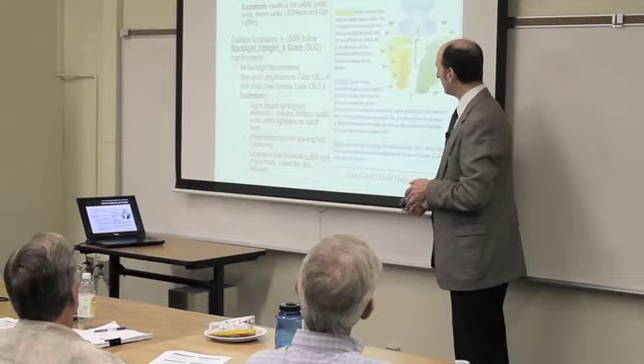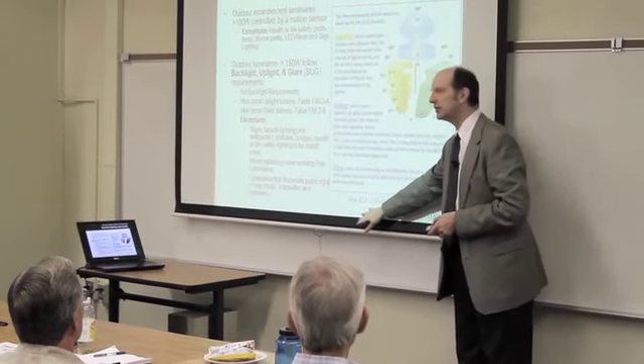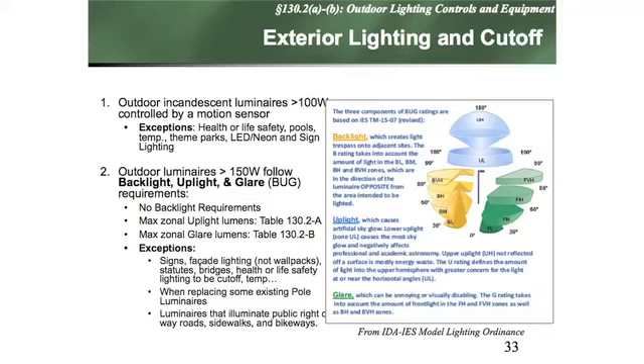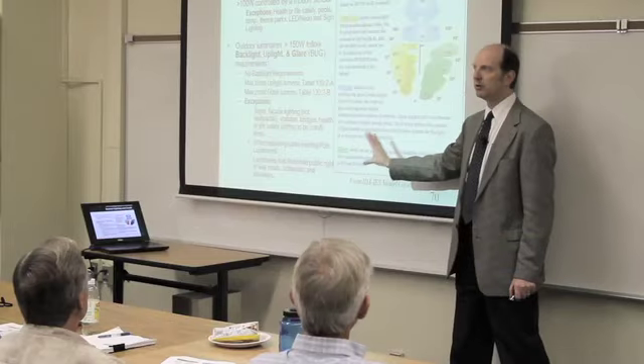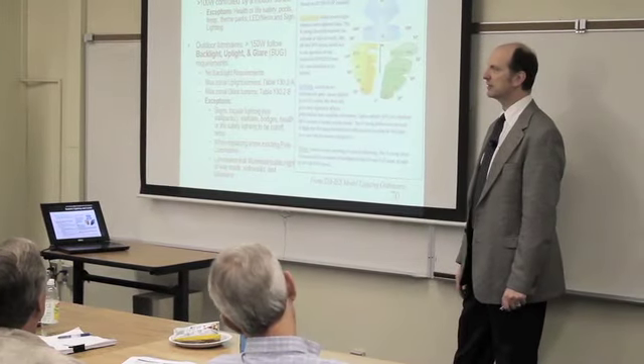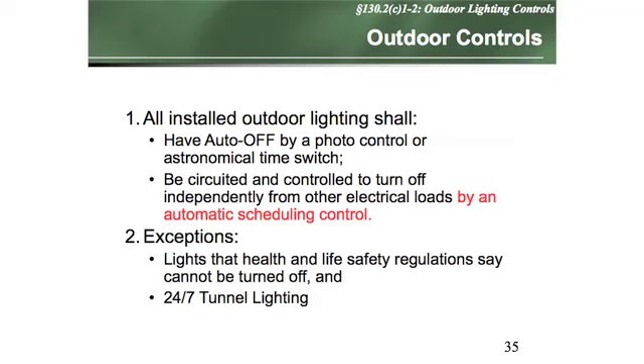So this is something that got put together actually by the International Dark-Sky Association and IES groups. So this is really attacking light pollution. By getting it into the energy code, they've covered the entire state of California and all buildings in it for the next 3 years at the very least. For controls for exterior, the requirements are to make sure they go off automatically by a photocell or time switch. There's this new requirement that says, oh, by the way, all exterior lights, even if you have them on a photocell, have got to be able to be turned off by an automatic scheduling system.